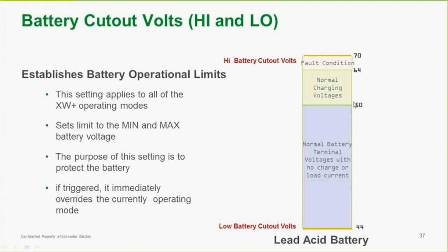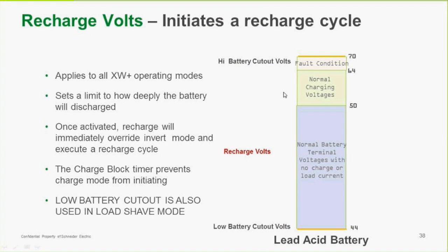We have a place where we need to start charging batteries when we do have the capability to charge, and the batteries will charge up to whatever is preset. If there's too much charging, there's a high level battery cutout, where the inverter will shut down. Recharge volts is the setting that initiates a charge cycle. I think that's pretty straightforward.